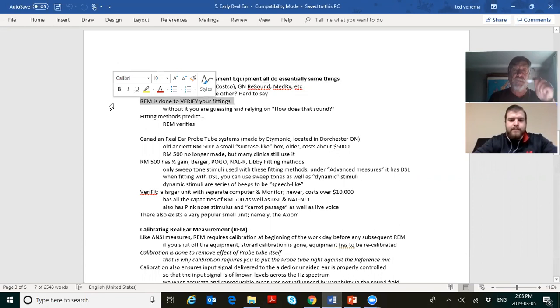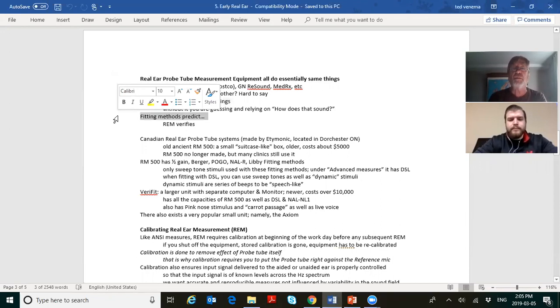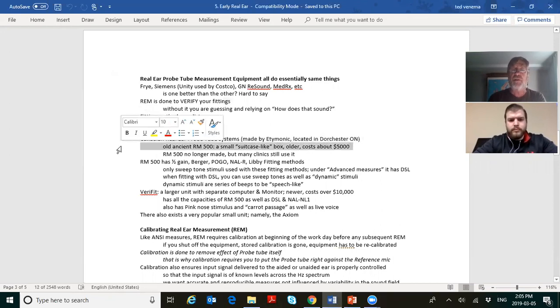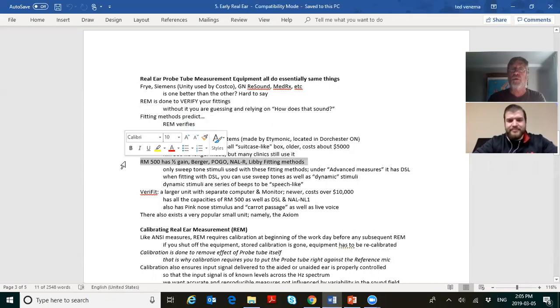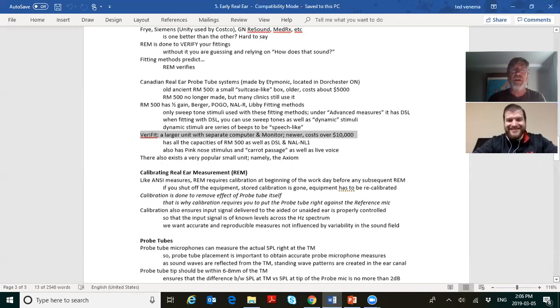But REM is done to verify fittings. Fitting methods predict, software predicts, real ear measurement proves. So the Canadian one is Etymotic, located in a weird town called Dorchester. The ancient old RM500 was a black, small suitcase-like box. No longer is made. Some clinics still use it, but that's if they're 150 years old. That old system only had half gain, Berger, Pogo, NAL, and Libby methods. Then they added DSL. VeriFit came out several years ago, a much larger unit, much newer, costs well over 10 grand, has all the capacities of everything. It'll even start your car and make you coffee in the morning.